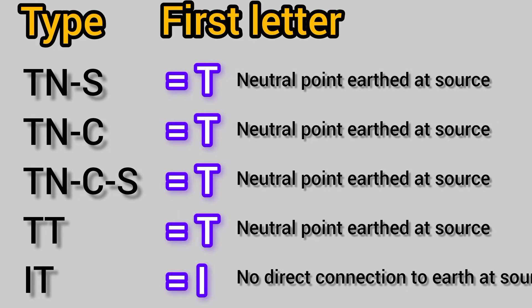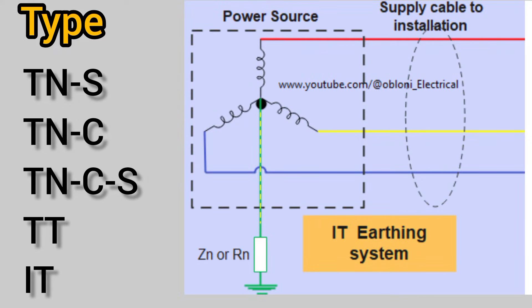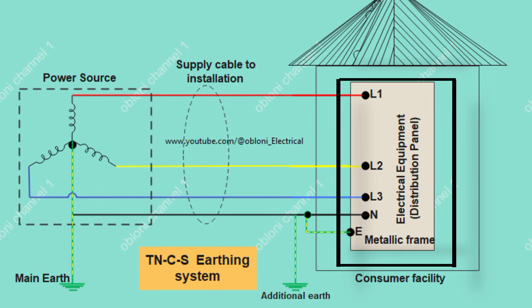The first letter denotes the source of power from a star-connected winding. If the first letter is T, it means that the star point of the source is solidly connected to earth. If the first letter is I, it means the star point of the source, or the star point of the transformer, is not directly connected to earth. The second letter refers to the consuming equipment that needs to be earthed — in this case, the consumer installation.